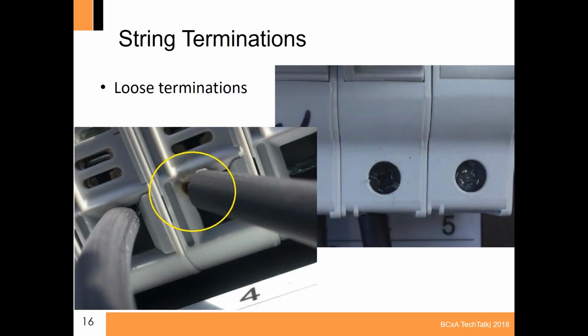In this example here, this is a close-up of the fuse terminal inside the inverter. What we can see here is a discolored screw, and then we look more closely on the left-hand side, we could actually see some thermal damage from this conductor. And actually, this connection was very loose, it heated up, and that caused the fuse to blow. So the problem could have been literally inches away from the fuse. In that case, our investigation showed if we replace this termination, we should be in good shape.